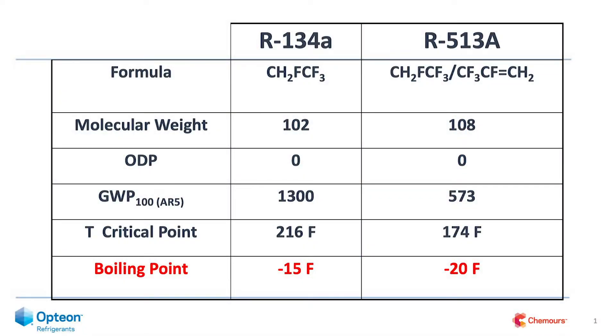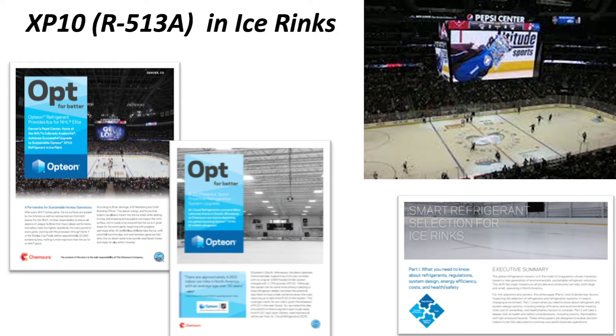It's not just medium temperature — I'm going to put some boiling points up here, and you can see there's a slight advantage to R513A over R134a with a lower boiling point. We are using it quite commonly in low-temperature applications, particularly ice rinks. There are a number of equipment manufacturers with very efficient ice rink chillers that operate down in the zero-degree Fahrenheit evaporator range and use R513A. It's a good solution for those types of applications.